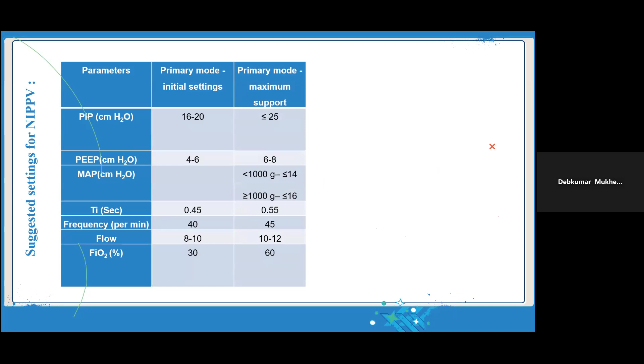So when you are using it as a primary mode, PIP you set around 16 to 20, PEEP 4 to 6, Ti 0.45 second, frequency 40, flow 8 to 10 liters if you adjust the flow manually. But if it is automatically adjusted flow, then you don't have to set it. FiO2 to 30%. As a primary mode, maximum you can go up to 25, PEEP maximum you can go 6 to 8, MAP you can go less than 1 kg 14, more than 1 kg 16.